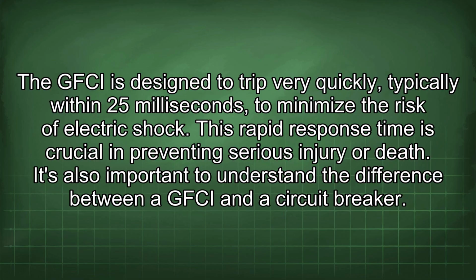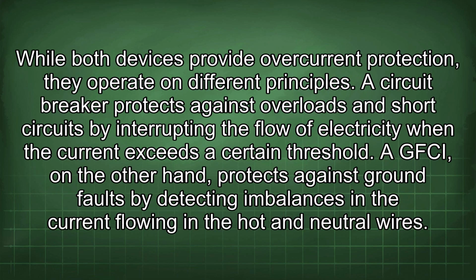This rapid response time is crucial in preventing serious injury or death. It's also important to understand the difference between a GFCI and a circuit breaker. While both devices provide overcurrent protection, they operate on different principles. A circuit breaker protects against overloads and short circuits by interrupting the flow of electricity when the current exceeds a certain threshold. A GFCI, on the other hand, protects against ground faults by detecting imbalances in the current flowing in the hot and neutral wires.